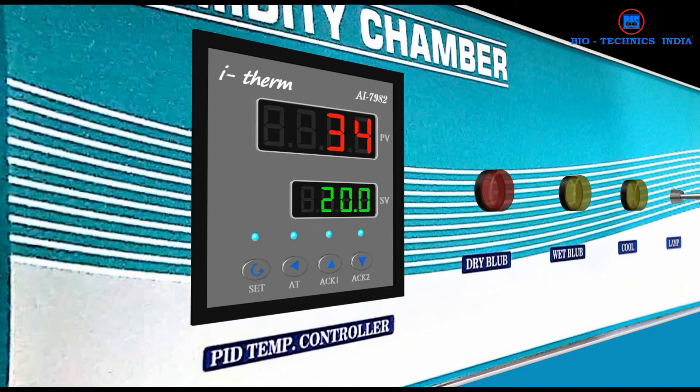If the temperature is fluctuating, press auto-tune key and select yes option and press set key. It will automatically reach the set value.